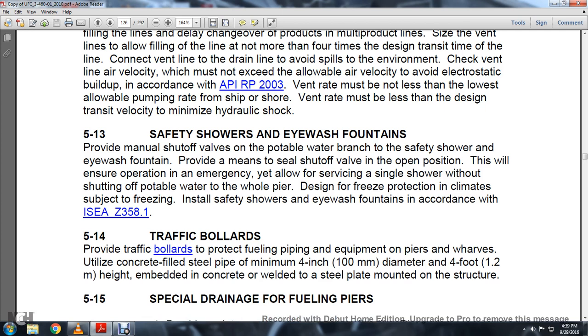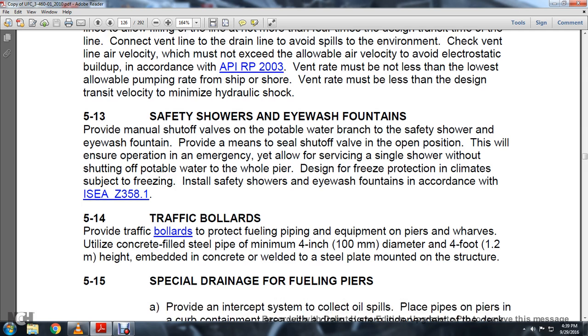Section 5.14 Traffic Bollards: Provide traffic bollards to protect fuel piping and equipment on piers and wharves. Utilize concrete-filled steel pipe with a minimum 4-inch diameter and 4-foot height, embedded in concrete or welded to a steel plate mounted on the structure.